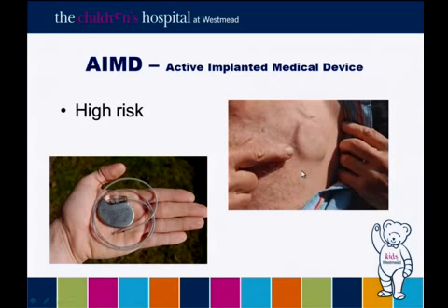And the characteristics of the electrode that's implanted into your ventricles or your atrium or both, depending on what type of pacemaker it is, such as the impedance and resistance between those electrodes and your tissues, change over time as well. So if you've got a pacemaker, you normally need to go in probably every 6 months. Some people maybe don't go quite so often, even if everything's going all right, and they analyse the output of the pacemaker and tune it all up, okay?